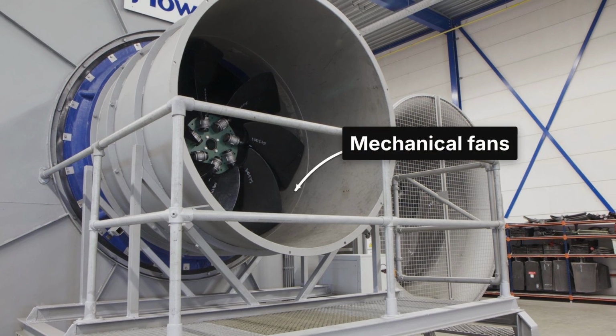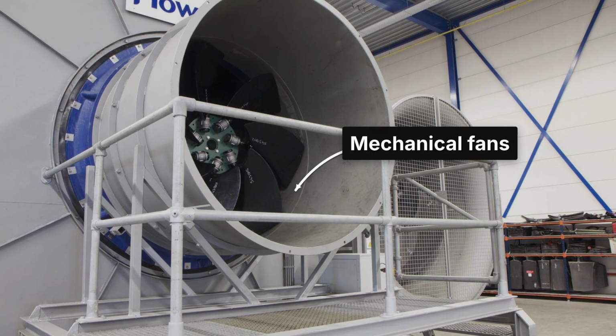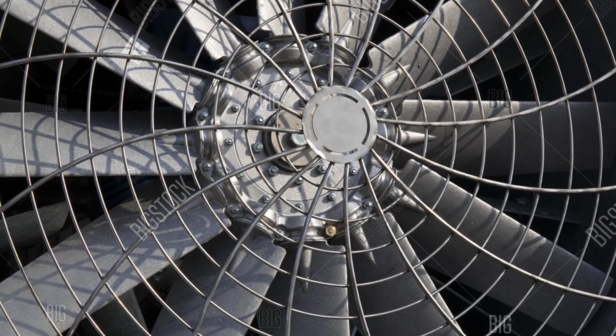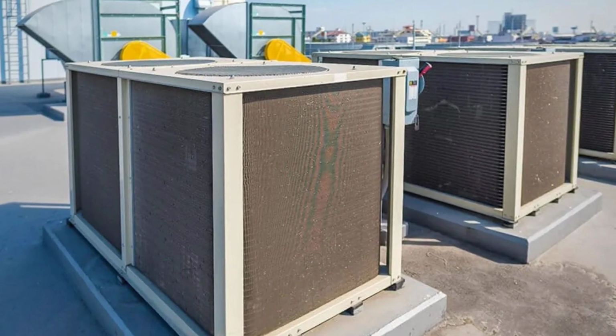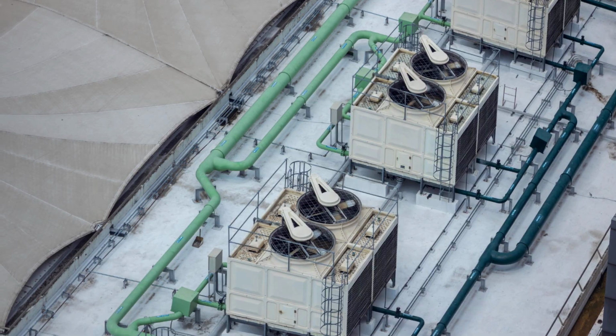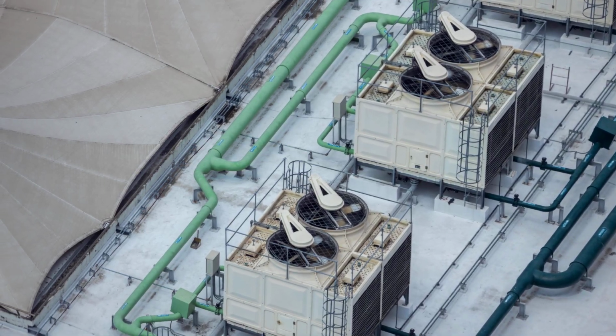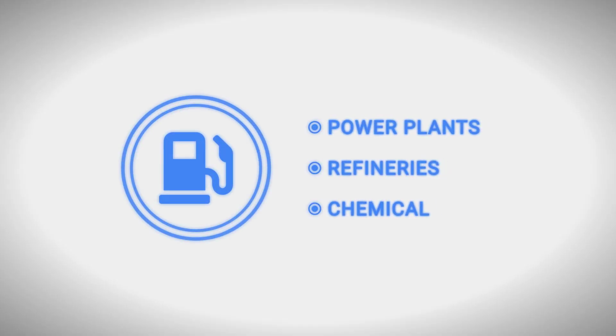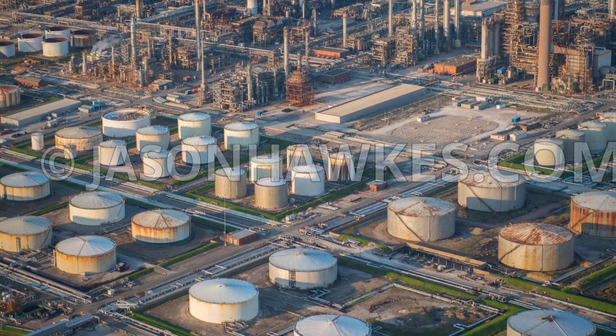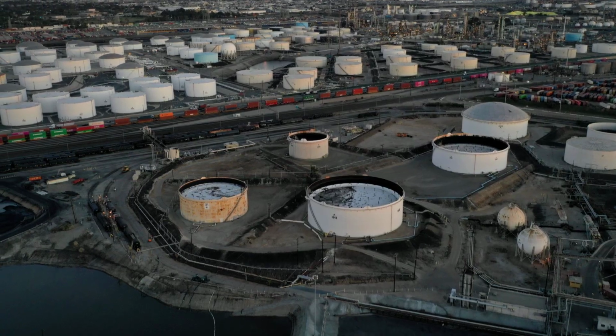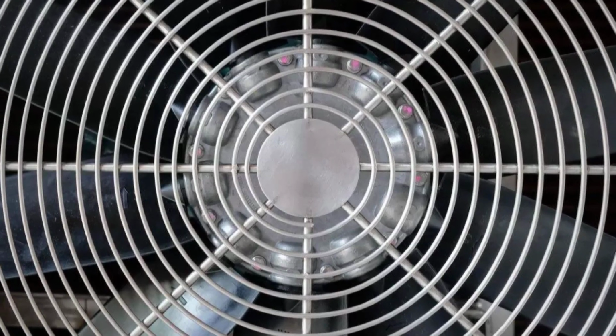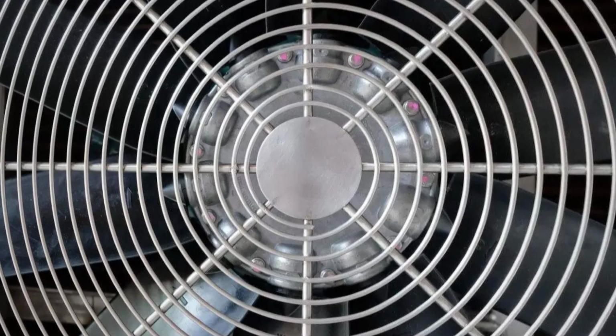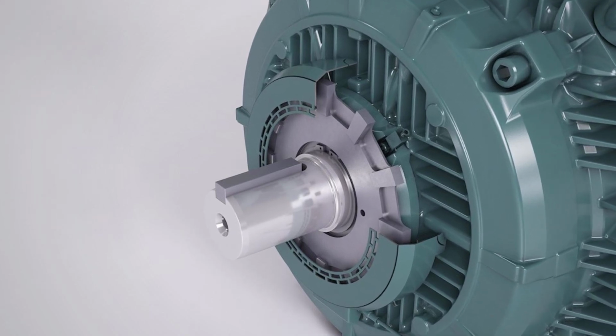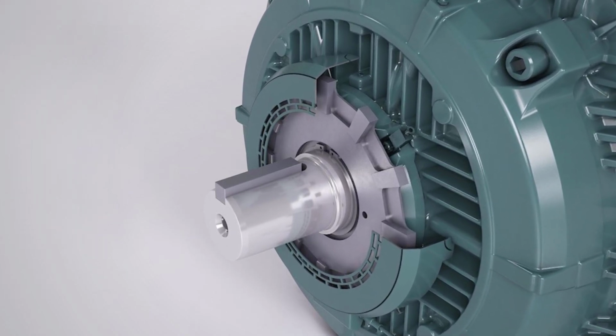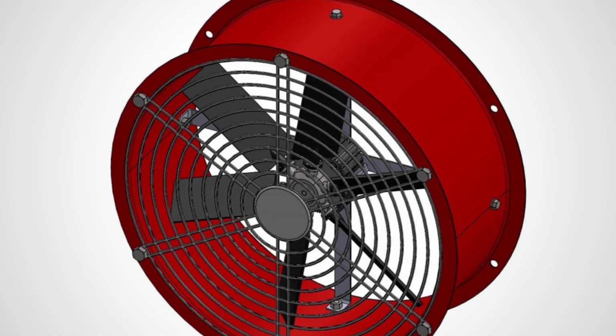These towers often employ mechanical draft systems, using fans to create airflow instead of tall stacks. Even if they don't always possess the towering height, these systems are still broadly referred to as cooling towers. In fact, many power plants, refineries, and chemical plants also utilize mechanical draft cooling towers. Mechanical draft systems are less reliant on ambient conditions for airflow, are generally smaller, typically less expensive to construct, and provide greater flexibility when heat loads fluctuate.